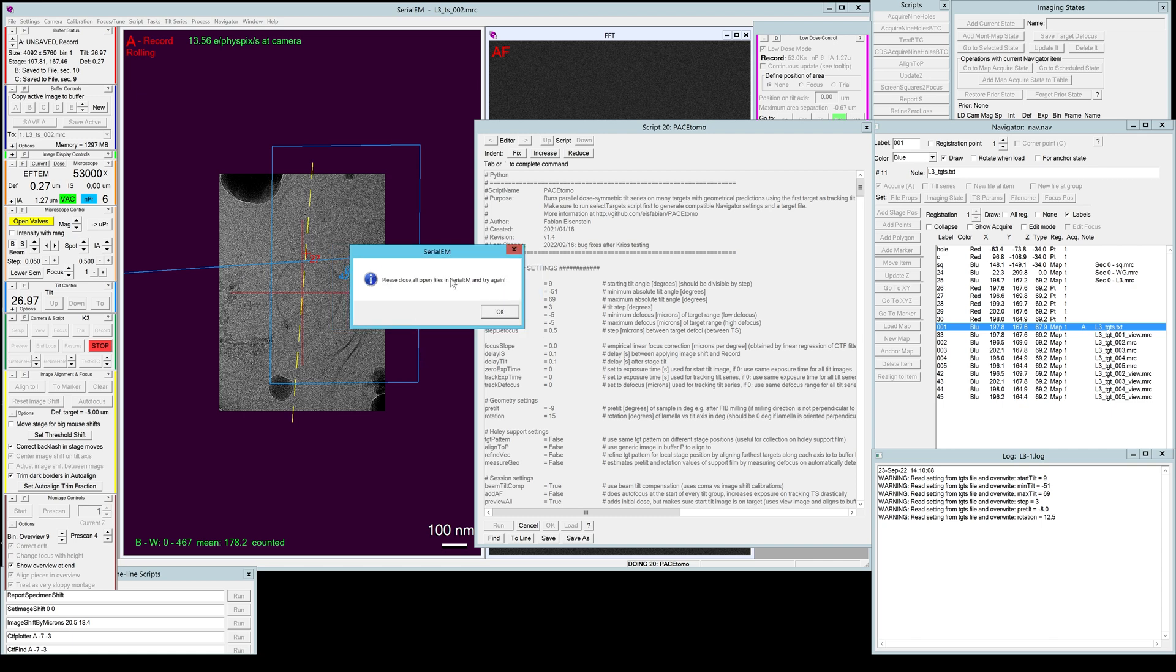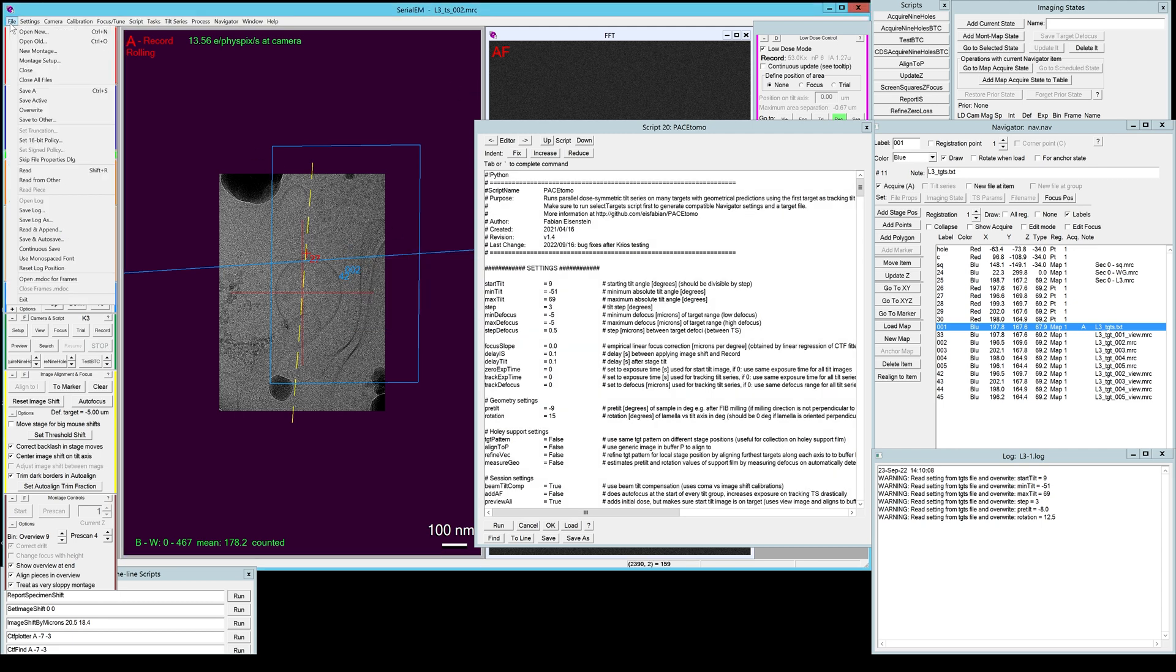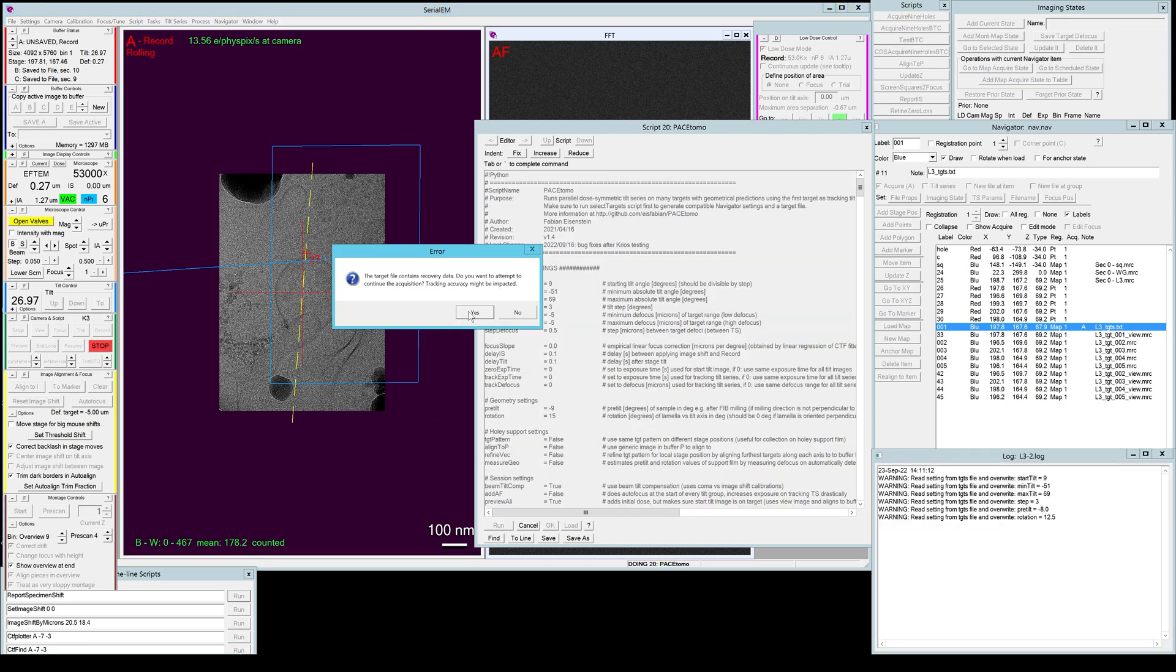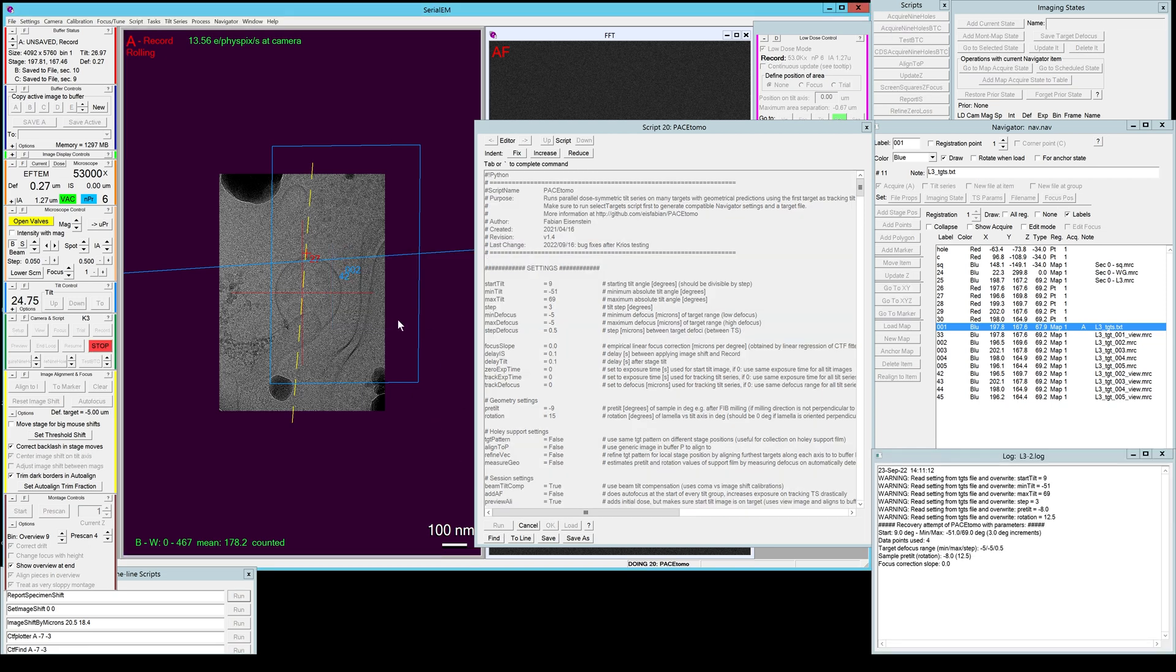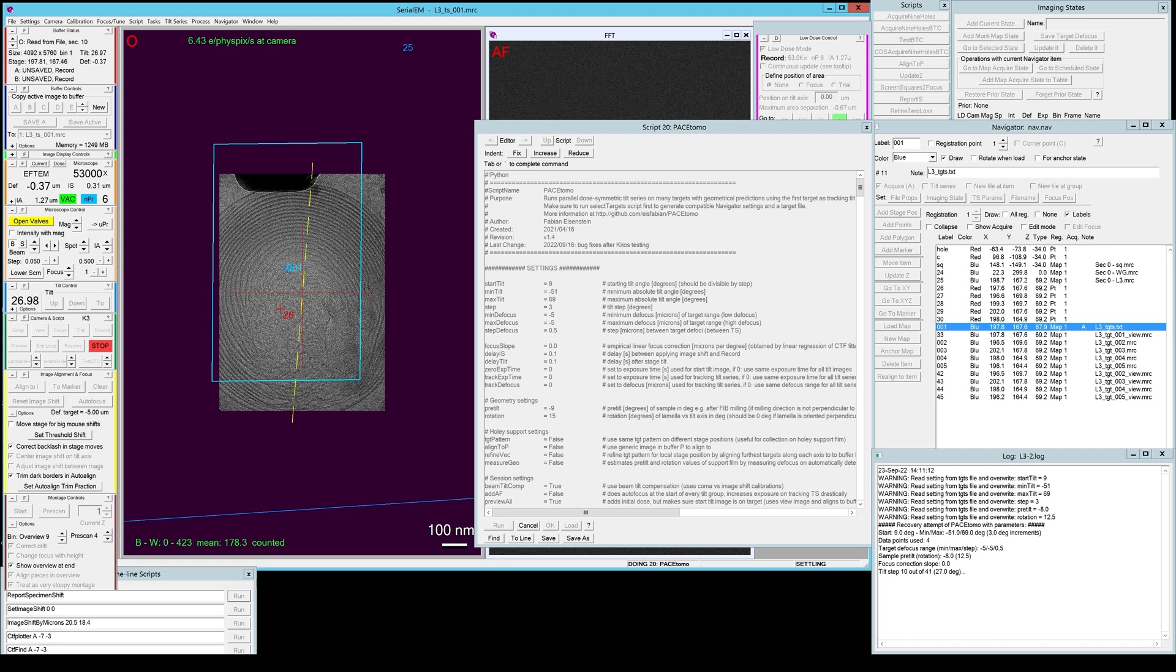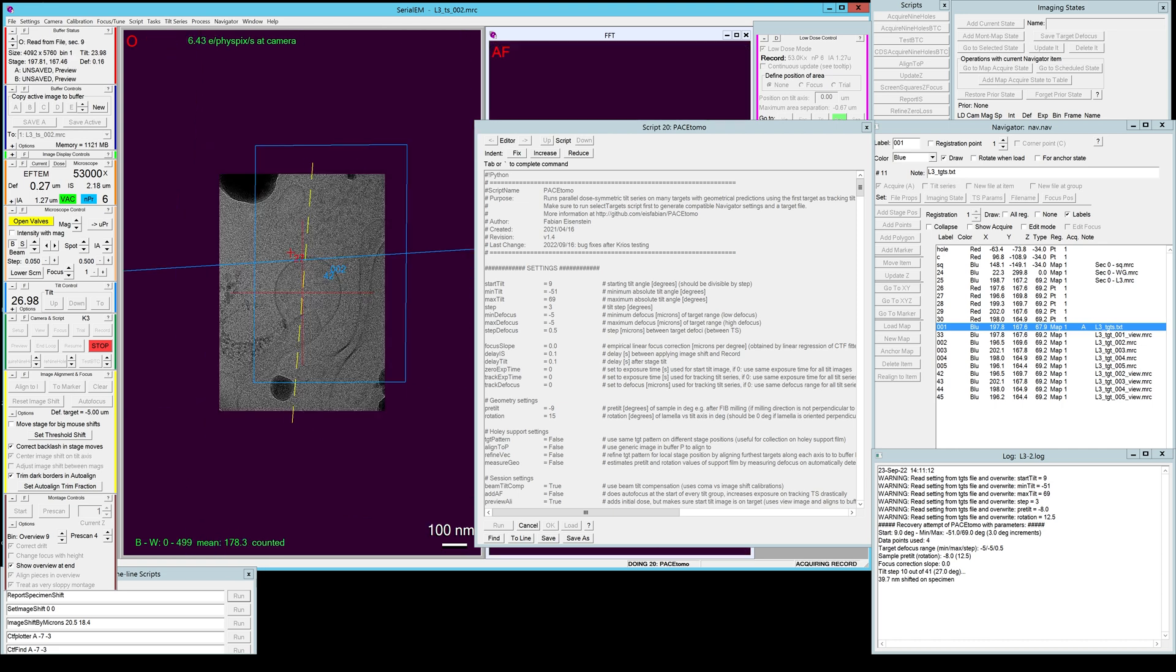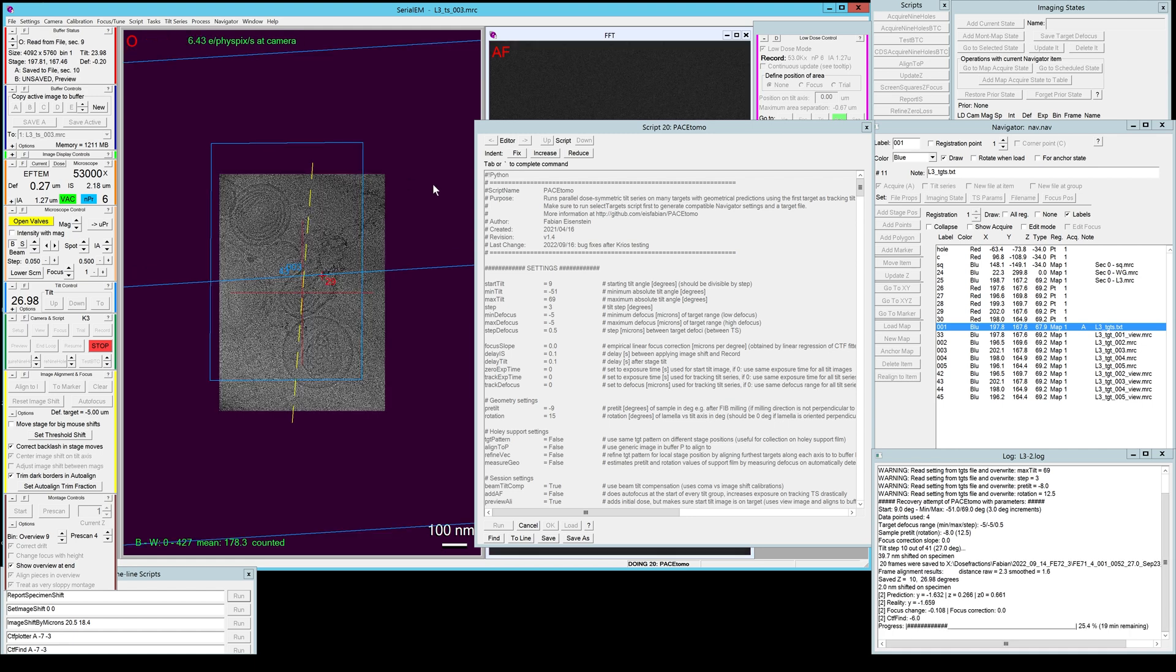So let's recover. It detected that one of the tilt series files is still open, which causes some trouble when SerialEM tries to open it while it's already open. So it asks you to close them. So let's go to file, close all files, and try this again. And it will plot in the log the recovery attempt. As you can see here, it saved quite a few options from before, and it will go back to where it started. And you can see how bad the error is in this case. And you can see it's basically non-existent. It's as good as it was before it stopped running.